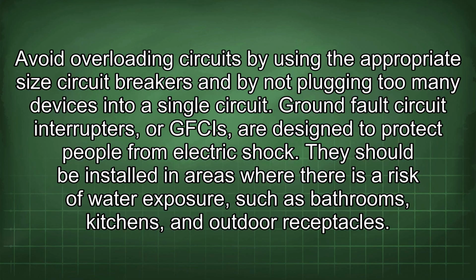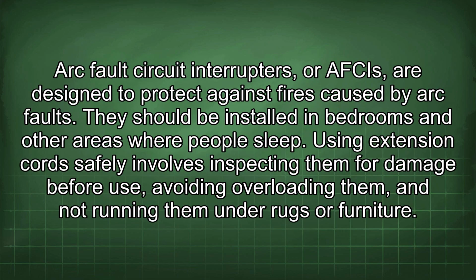Ground fault circuit interrupters, or GFCIs, are designed to protect people from electric shock. They should be installed in areas where there is a risk of water exposure, such as bathrooms, kitchens, and outdoor receptacles. Arc fault circuit interrupters, or AFCIs, are designed to protect against fires caused by arc faults. They should be installed in bedrooms and other areas where people sleep.